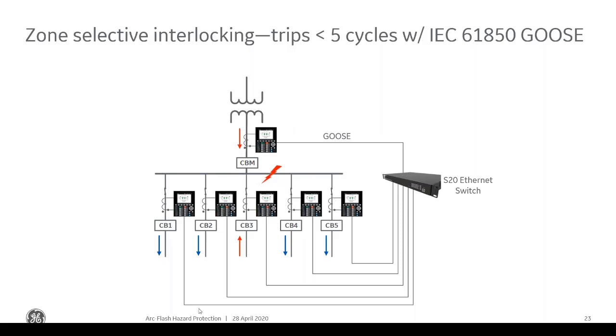Very easy to implement. All relays today have some sort of communication port which supports IEC 61850 GOOSE messages. At least ours do, all of ours do. Easy to implement, just adding some sort of switch. You can have 2 switches if you want redundancy. All our relays have up to 2 ports on them.